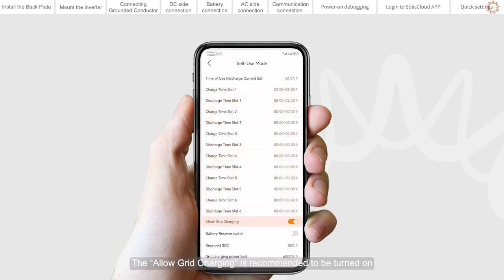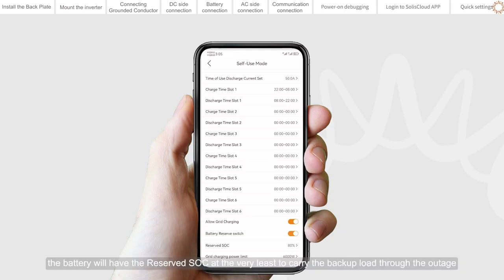The allow grid charging is recommended to be turned on. Backup mode can be opened in the self-use or feed in priority mode. You can set the reserved SOC. If grid power is lost, the battery will have the reserved SOC at the very least to carry the backup load through the outage.